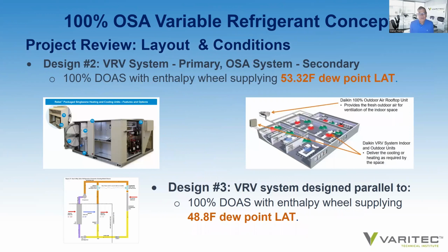Design number two was a variable refrigerant system as the primary HVAC system, and then we provided the DOAS outside air system as the secondary unit. So we used a 100% outside air Daikin Rebel unit with an enthalpy wheel to precondition the outside air, and we selected the coil at a size that we could hit a dew point of 53.32 degrees, which is the leaving air condition of 55 degree dry bulb, 54 degree wet bulb.